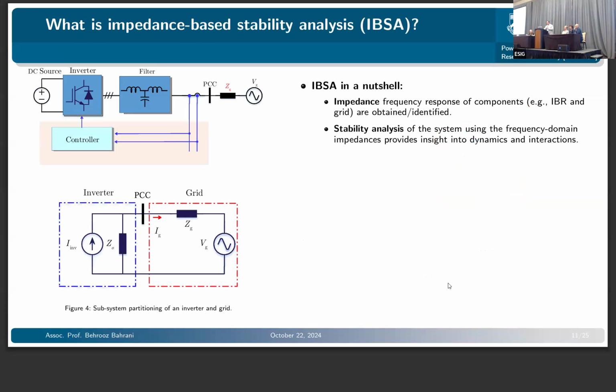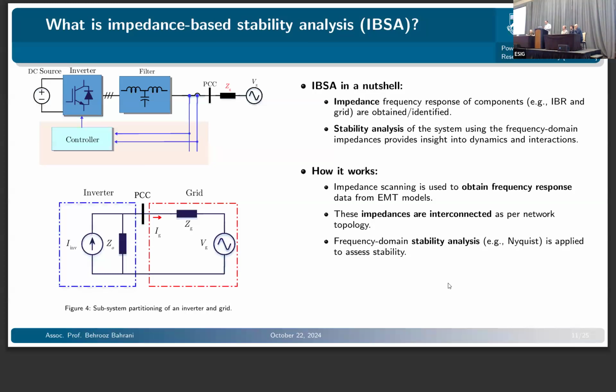Imagine we've got one inverter connected to the grid, and you want to do impedance-based stability analysis. In a nutshell, the idea is to identify or obtain the frequency response impedance of the grid and the IBR, and use some stability criteria - in this case Nyquist stability criteria - to assess the stability. You first need some sort of EMT model; a black box EMT model of the IBR is very suitable for this.